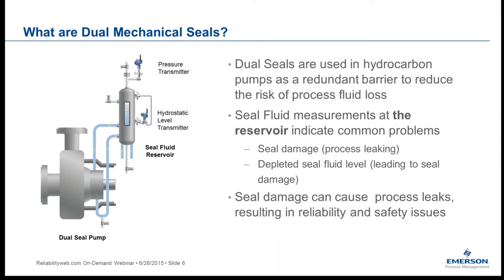Dual mechanical seals were developed to reduce the risk of process fluid loss. With a single mechanical seal, if the seal fails you have a release of process fluid — and in refining and petrochemical plants, the process fluid is always either flammable, toxic, or sometimes both. In Plan 52 the fluid is called a buffer fluid; in Plan 53, where it's pressurized, it's called a barrier fluid. Either way, the function is to provide lubrication and cooling to the mechanical seal faces, because loss of this flush fluid leads to rapid seal damage and failure.